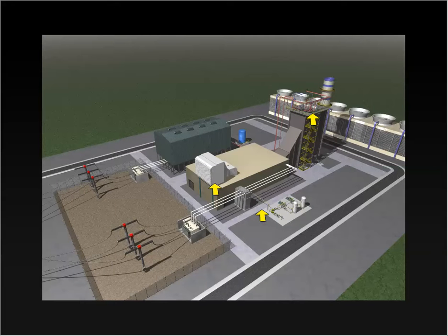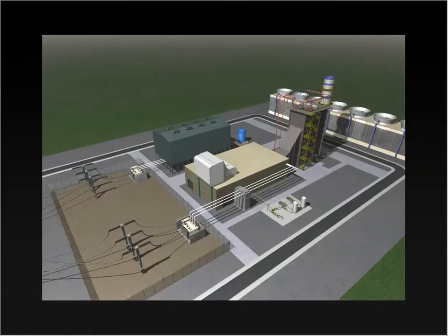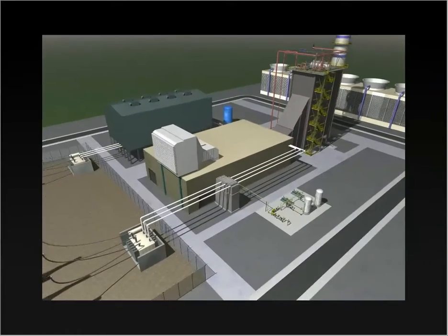This is a 20 megawatt combined cycle power plant, which burns natural gas to create electricity. First, natural gas is burned to power a gas turbine, which is hooked up to a generator. The gas turbine is the major producer of electricity and creates 17 megawatts. The exhaust from this gas turbine is directed to a heat recovery steam generator, which creates steam to be sent to a second turbine. The smaller turbine, the steam turbine, creates 3 megawatts of electricity.